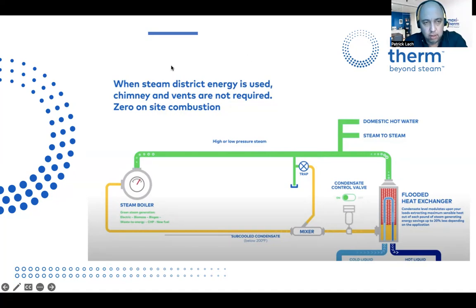We have installed, by the way, at the American Museum of Natural History, North Shore Hospital in Long Island, Vassar Hospital, not too far away from New York City, and Pepsi Cola, also nearby New York. So where I was going, depending on your temperature set point on the hot water side, let's say 120 Fahrenheit set point, which is a big trend right now with heat pumps and other applications to go low temperature set point, we can do the same.